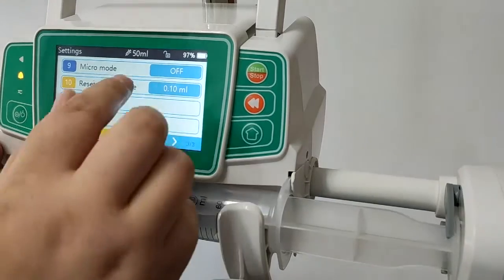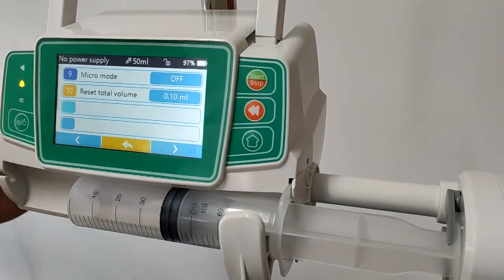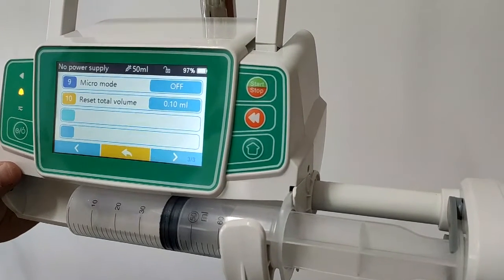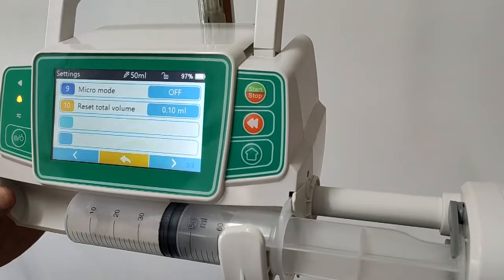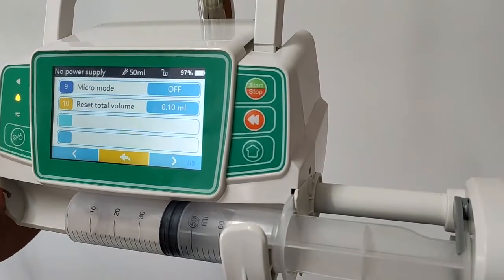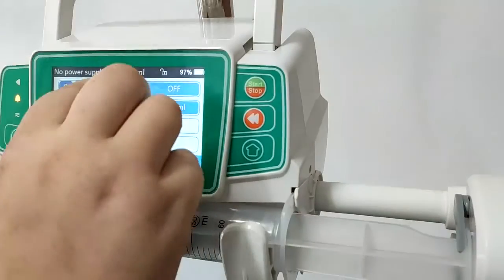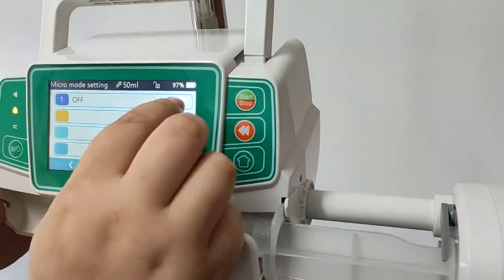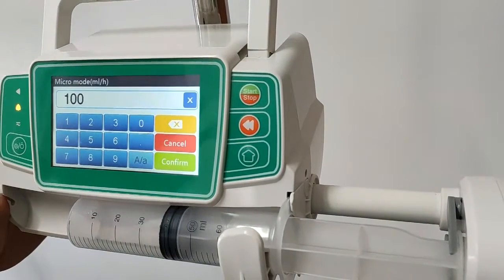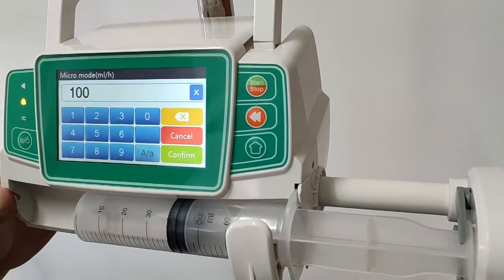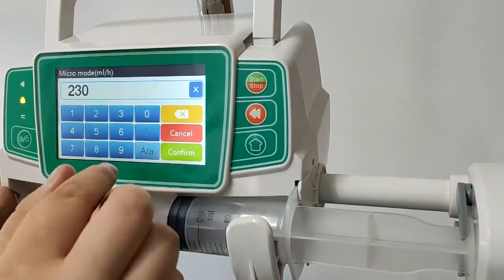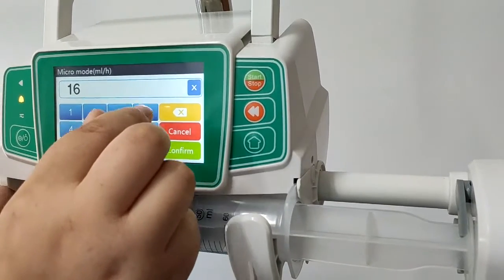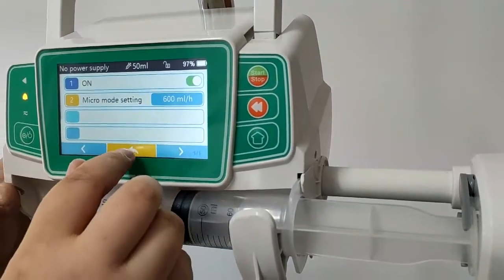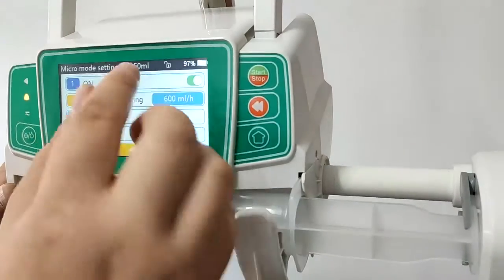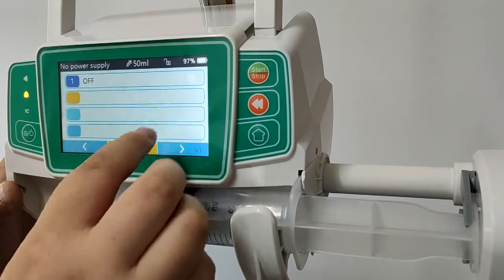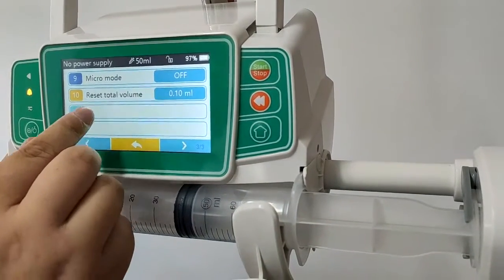And the third page will be micro mode. By micro mode, because sometimes by mistake, maybe the nurse will input 1,500 ml per hour instead of 150 ml per hour, which is very dangerous to patients, especially the newborns or small babies. For example, by default it's turned off. You turn it on and you choose the rate. The minimum rate for the micro mode is 100 ml per hour. You can set 230 or 600 and turn back. And if you have micro mode on, no speed more than 600 ml per hour will be okay. Okay, we'll turn it off and go back. And you can also reset total volume here.